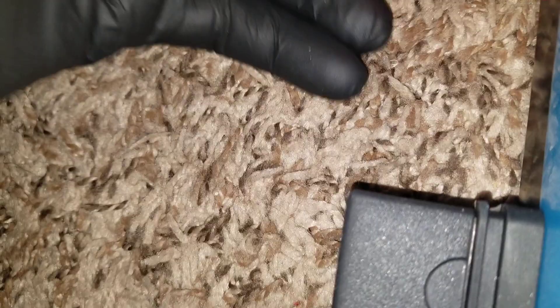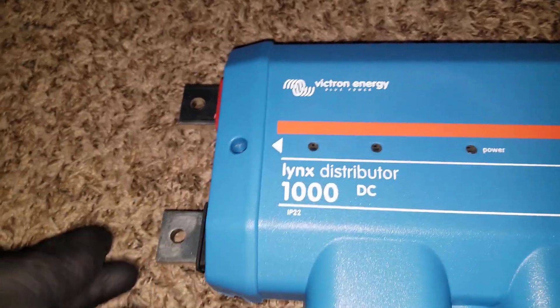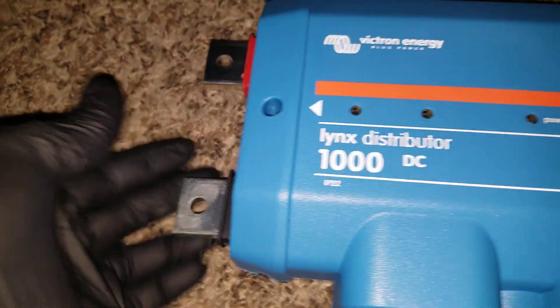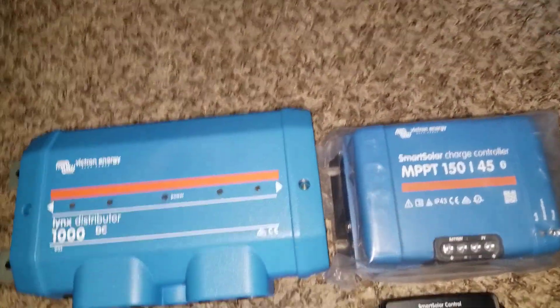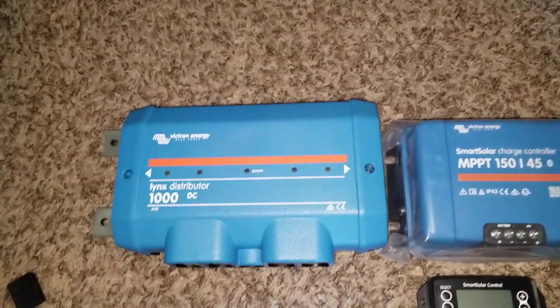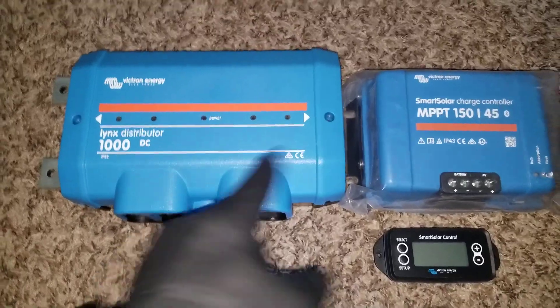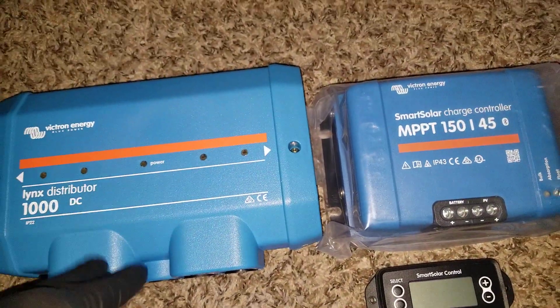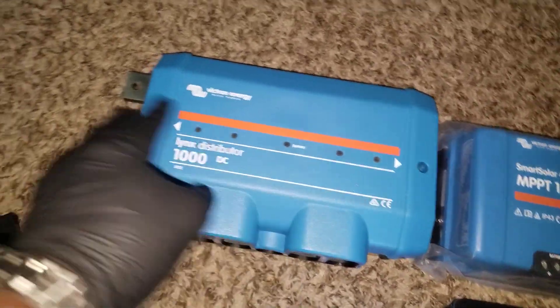It connects to these bus bars — and the bus bars are really beefy, really tough. These are huge; you can see how thick they are, approximately half an inch thick. This one sticks into the Lynx Distributor, which is the 1000-amp unit. They feed from here and you can extend them — one, two, three — as much as you need for your distribution. Charge controllers and inverters can connect into this.